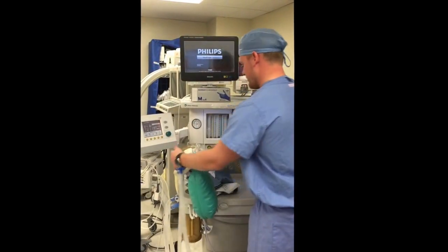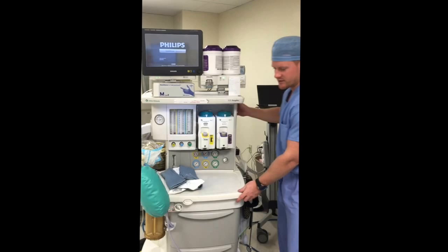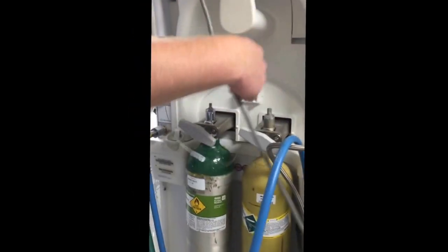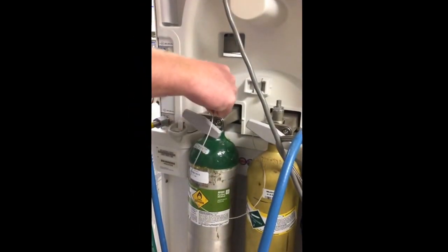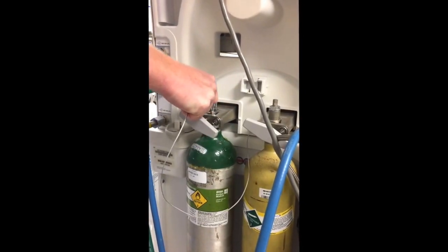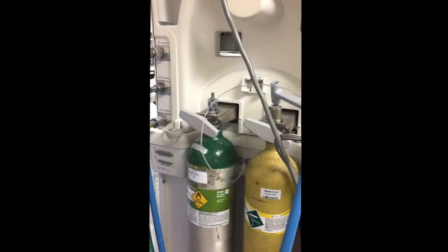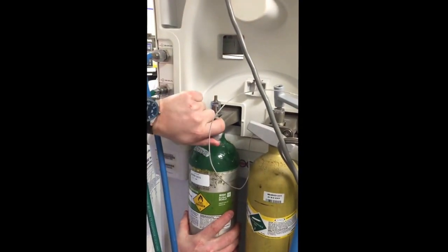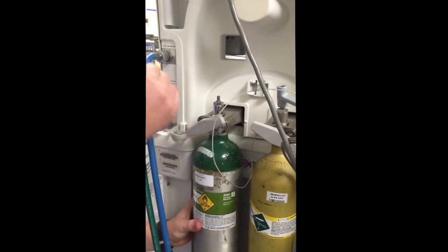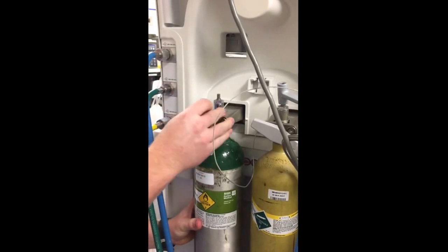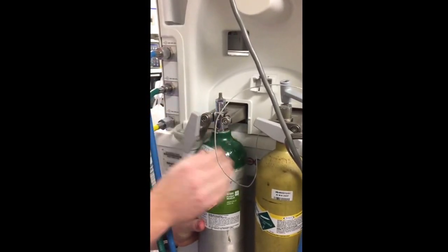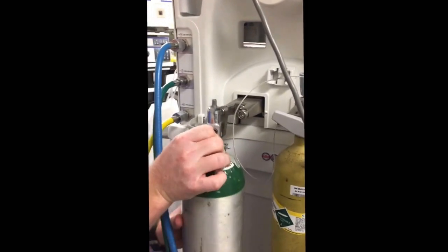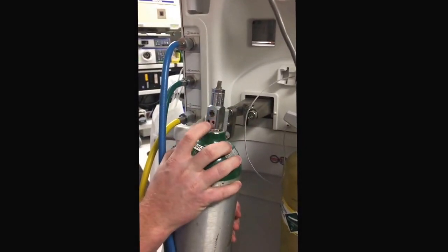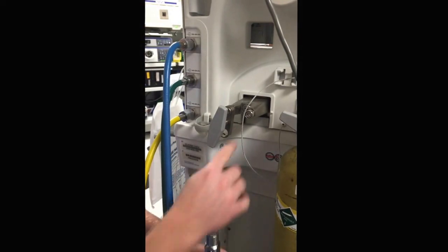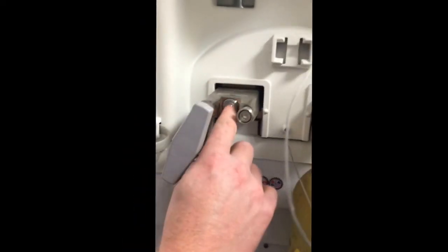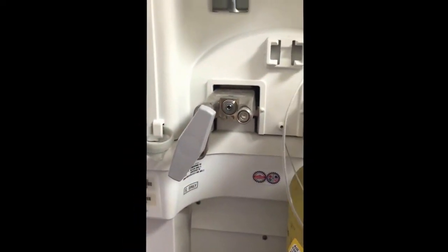The last thing I'll show you is in the event that you would have to change an oxygen cylinder, which you will. So when changing the O2 cylinder, you want to make sure that it's completely off. Hold the cylinder by the body, untwist the holder, pull the cylinder off. As you can see, the correct pin index safety system, and always check to make sure proper O-rings are intact and not aged.